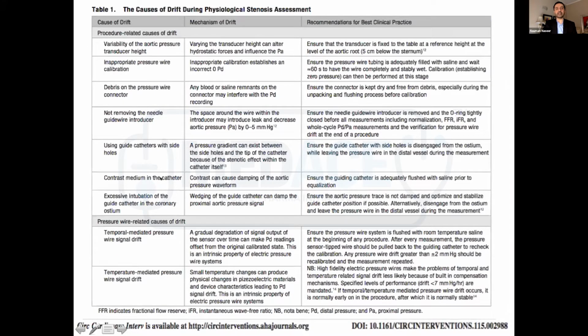These are all the mechanisms. These are technical reasons: variability of the aortic pressure transducer, post-measurement inappropriate pressure wire calibration, debris on the pressure wire connector, not removing the needle introducer, using a guide catheter with side holes, contrast medium in the catheter. So always flush the catheter during measurement, take the introducer out, and make sure during measurement you don't have any debris on the pressure wire connector, especially when you're reconnecting. And excessive intubation of the guide catheter can also make false measurements.